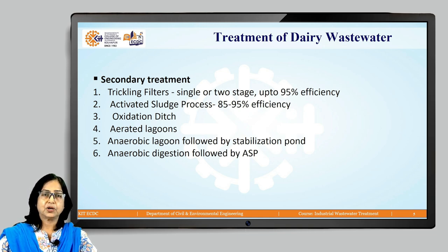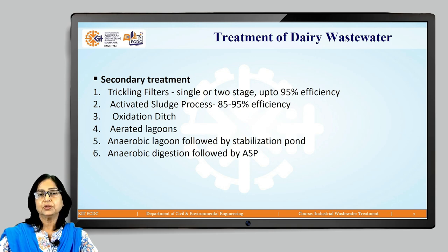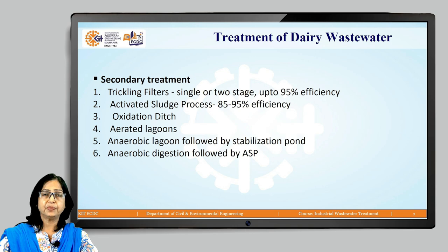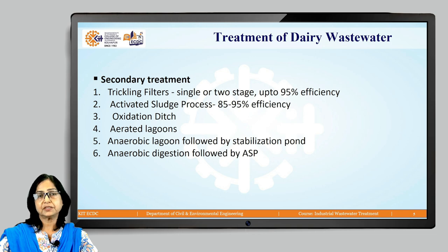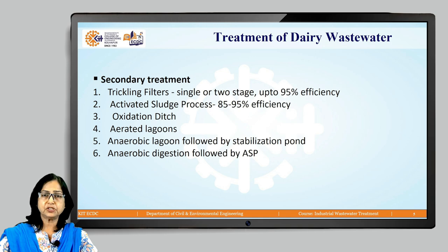Since the initial BOD of dairy wastewater is high — about 1000 mg/L — a combination of anaerobic treatment followed by aerobic treatment is a cheap and efficient alternative. When a digester or UASB is employed, it also enables recovery of methane gas or biogas. An anaerobic lagoon followed by a stabilization pond is also preferred, and another alternate treatment is anaerobic digestion with biogas recovery followed by the activated sludge process. All these treatments give high efficiency and can achieve disposal standards for dairy wastewater.